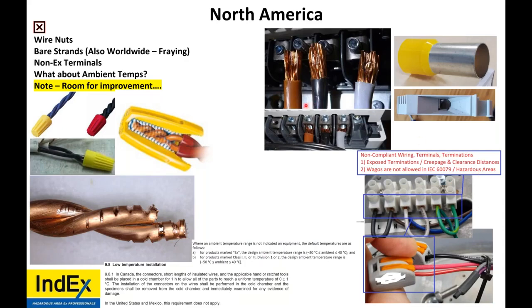Now, what about this one, the one in the top center? This is a typical North American technique. I know because that's where I came from. Even if this is not EX, it's a poor way of doing terminations. Now, what's the problem? The exposed strands, for one, and two, the terminal types, how the post goes down where it doesn't have a flat surface evenly distributing pressure, is quite poor. So what could they do? Different terminal types and use ferrules. It would increase the quality of your terminations, lessen chance of failures.